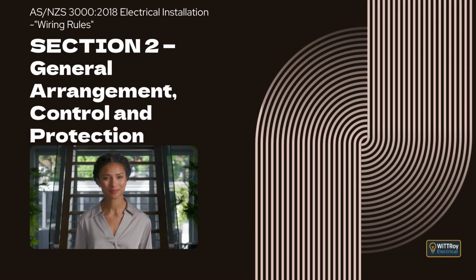Clause 2.5.4.5, omission of short-circuit protection, explains that in special cases, short-circuit protection may be omitted altogether. This is permitted only where automatic disconnection could create a greater danger than the short circuit itself, where consumer mains are installed in accordance with the special rules for unprotected mains, or where conductors connecting generators, transformers, rectifiers, or batteries to their switchboard meet strict installation conditions.